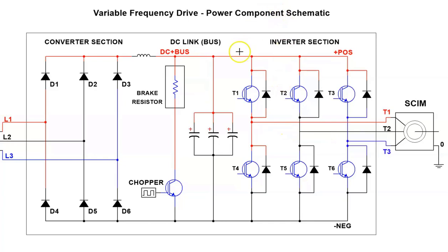Bottom line is the DC bus voltage is going to increase. If it increases to an unsafe level, you will get an overvoltage fault. But when you have a chopper circuit installed and either an internal brake resistor or an external brake resistor, that voltage and that rising level on the DC bus will be taken care of by this chopper circuit.